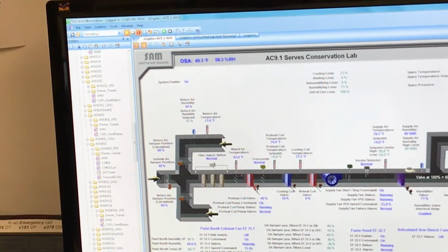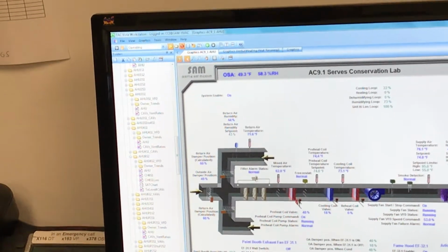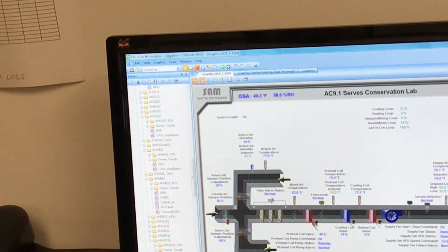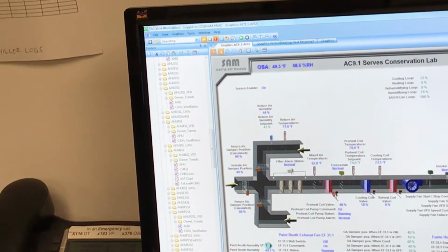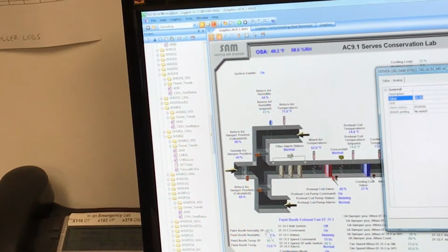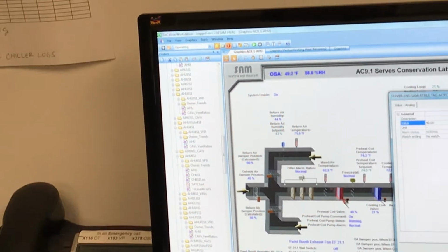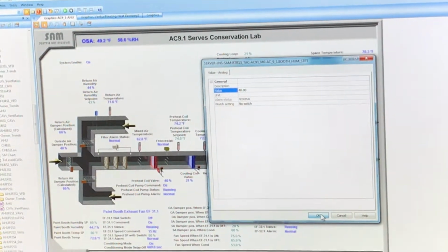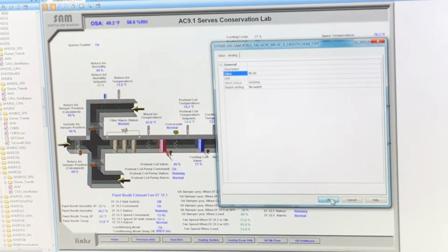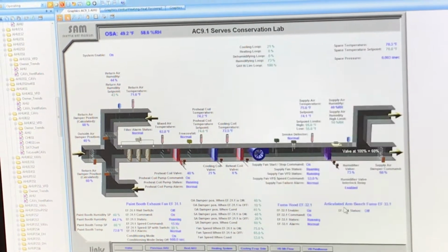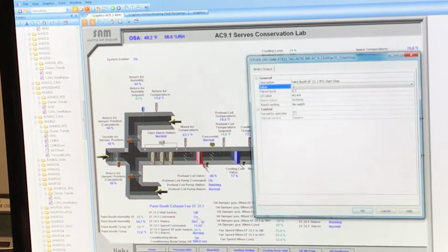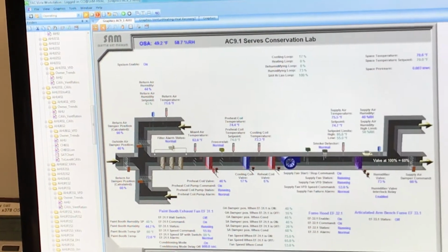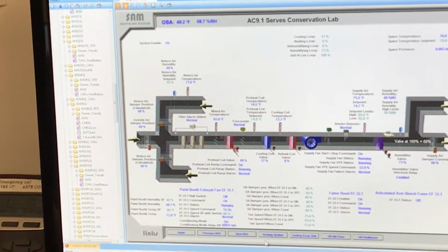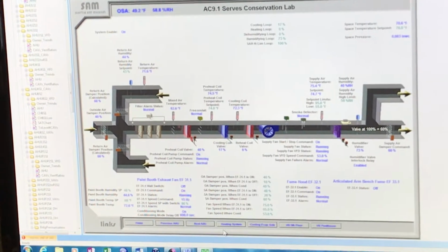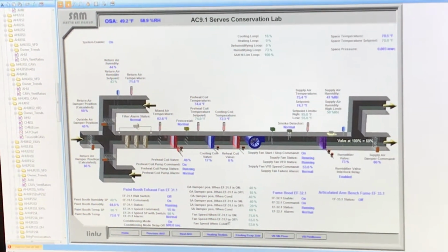Okay. But the condition is such that when the humidity is high, you want to try to start the fan with a minimum of exhaust air, to try to get the humidity out. And so what we put in the mode is that when the paint booth is sensing high humidity, we enable the fan and open the damper at the minimum speed to get some air through the booth and try to extract the moisture, no matter what. Yeah, I mean, that's what I was going to talk to you guys about after the training.